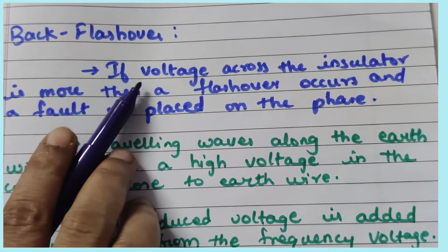Traveling waves along the earth wire induce a high voltage in the conductor close to the earth wire. This induced voltage is added to or subtracted from the frequency voltage, so at any instant at least one phase will have the same polarity as the lightning surge. Such a phase is more likely to flash over, hence this phenomenon is called back flashover.